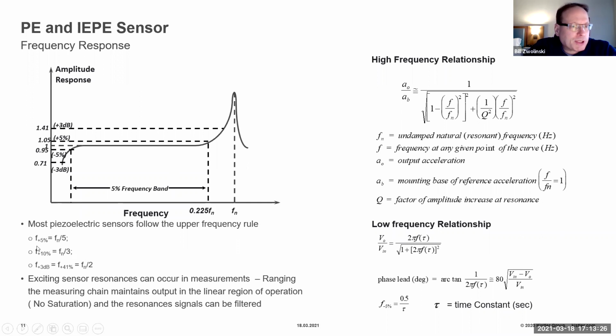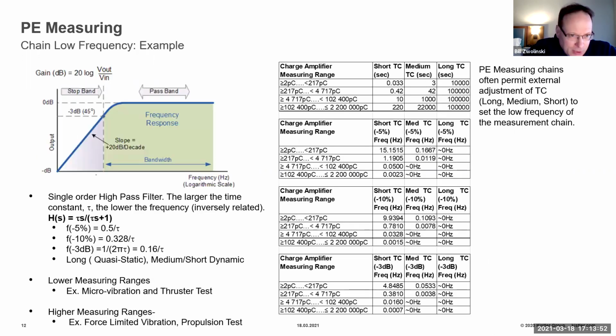So if you wanted to know the 5% frequency, a 5% amplitude response of a piezoelectric sensor, you would simply take the natural frequency divided by 5, and 10% would be the natural frequency divided by 3. A 10% response is where the amplitude response varies plus or minus 10% over a given frequency band. That's very helpful in terms of measuring some high frequency events, harmonics, and so forth. On the low end, it acts like a single order high pass characteristic, and that in the Laplace domain is given by this famous expression. Anyway, you can calculate closed form expressions for the frequency response in terms of the time constant, and you can relate what the effect of this roll off is at low frequency.